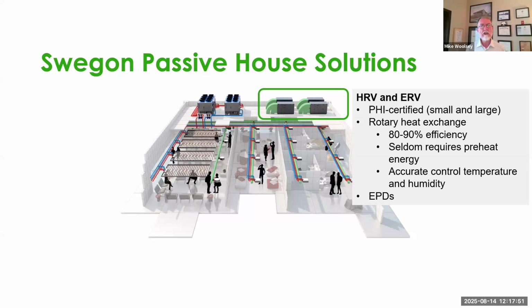We use a rotary heat exchanger; a lot of other people use plates. There are some nice advantages to rotary heat exchangers — they're just as efficient as plates. Because of the control strategy used with a rotor, we're able to operate with less frosting, so in most climates — you have to get pretty far north in Canada, or maybe Alaska — to get cold enough to require any electric preheat during frosting.